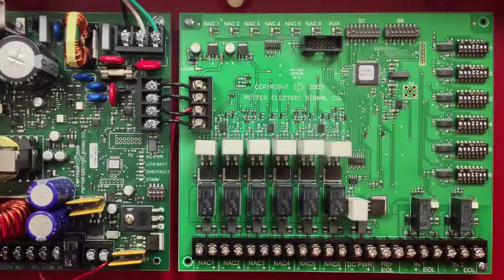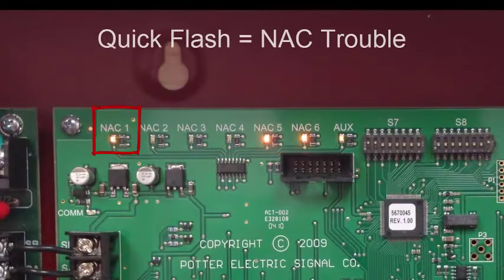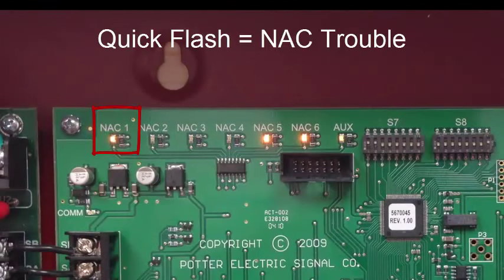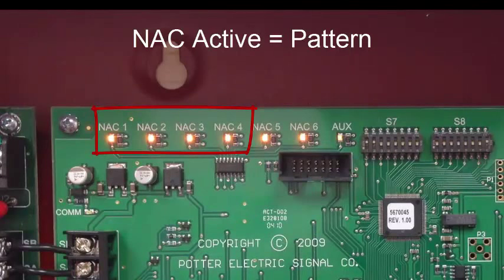Each NAC output has an indicator LED located at the top of the board. The LED will flash quickly when there is a trouble condition such as an EOL missing, EOL shorted, or current limit condition. When the NAC is active, the LED outputs the same pattern as the NAC output. So for example, when NAC1 is programmed as Gentex sync, when the NAC is active, the LED of NAC1 flashes in a Gentex sync pattern.